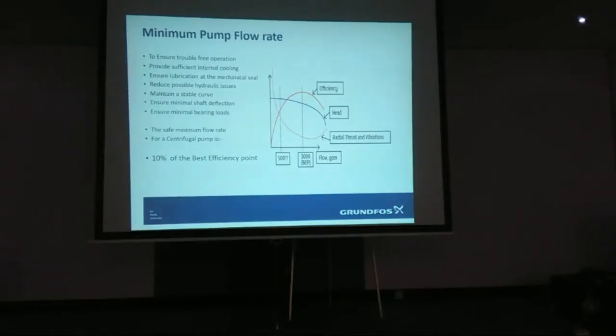So that's when you need to introduce bypasses at the end of loops, which you're wasting energy then, because the pipe's probably already up to temperature, you're just moving more water, so delta T is going to close up even more. What you want to do is increase delta T by reducing the flow.